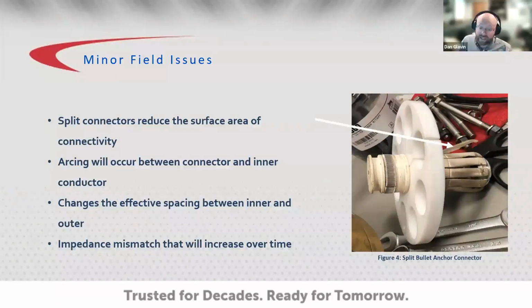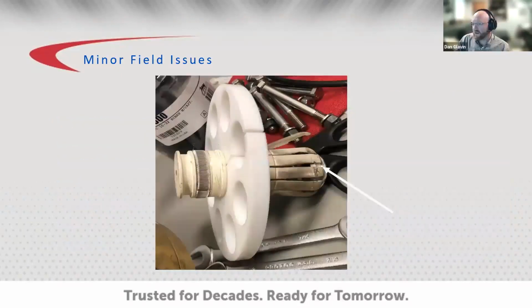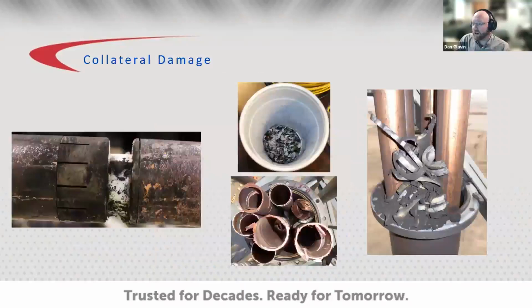It also creates a smaller air gap between the inner conductor and the outer conductor, which could potentially push it past the breakdown voltage of air and cause sustained arcing that can litter the entire transmission line system as well. These are very common as well. We see these from time to time, pictures from installation crews, so it's not an unfamiliar occurrence. You see the anti-split ring there.